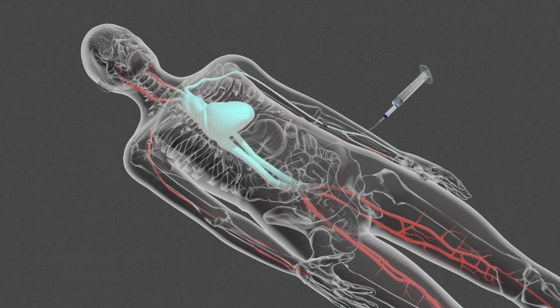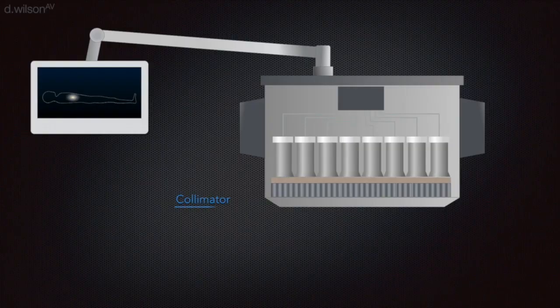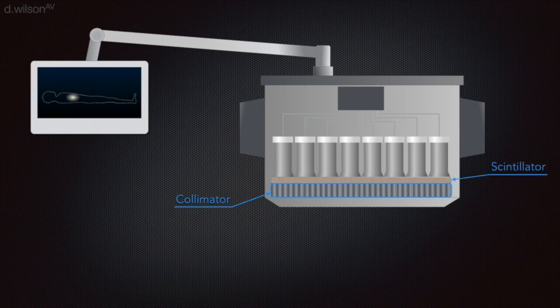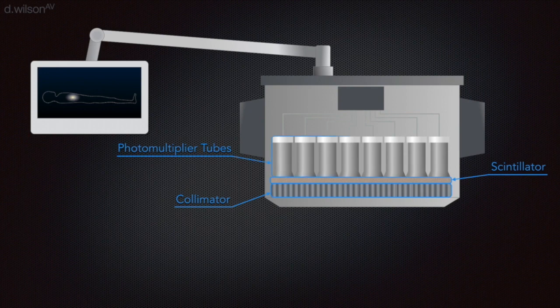The first part of the gamma camera is a collimator. It absorbs gamma rays that do not travel parallel to the plates, improving image resolution. The gamma rays that pass through the collimator strike a scintillation crystal.